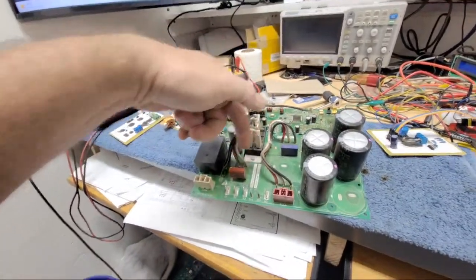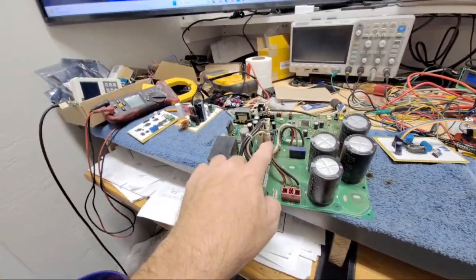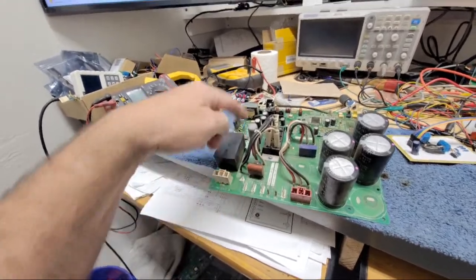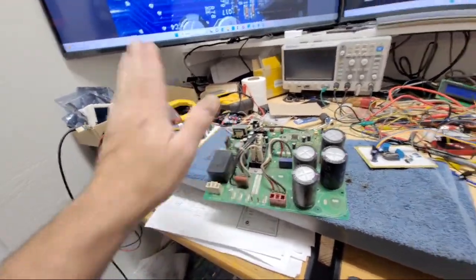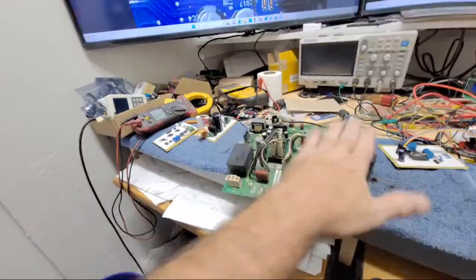This is a 3-phase one in this case. One leg goes directly to it, and the other two go through the bleed resistors, and then the relay, once it latches right after the inrush current charges these up, and then you've got your IPM power module here, and then your three outputs.